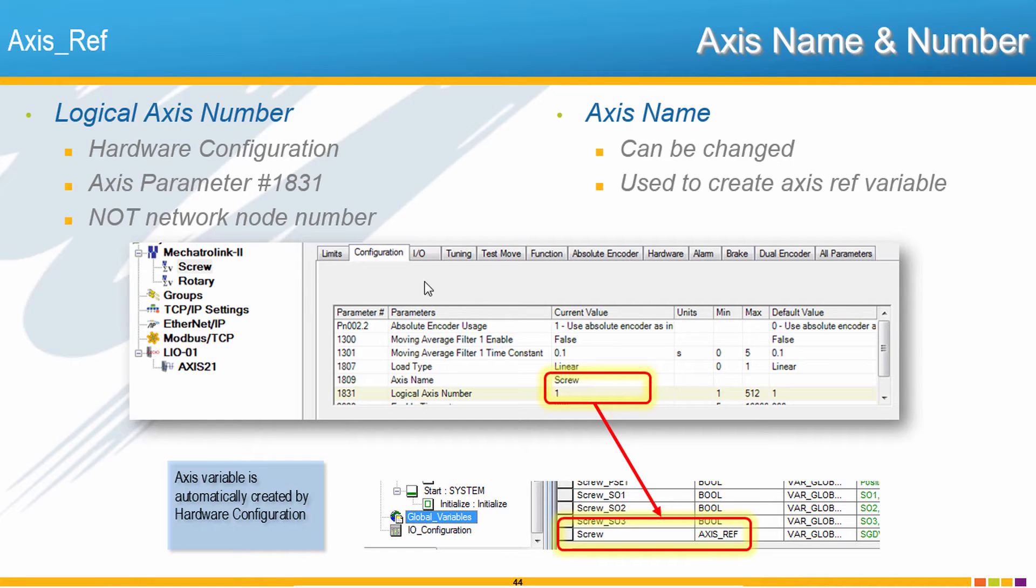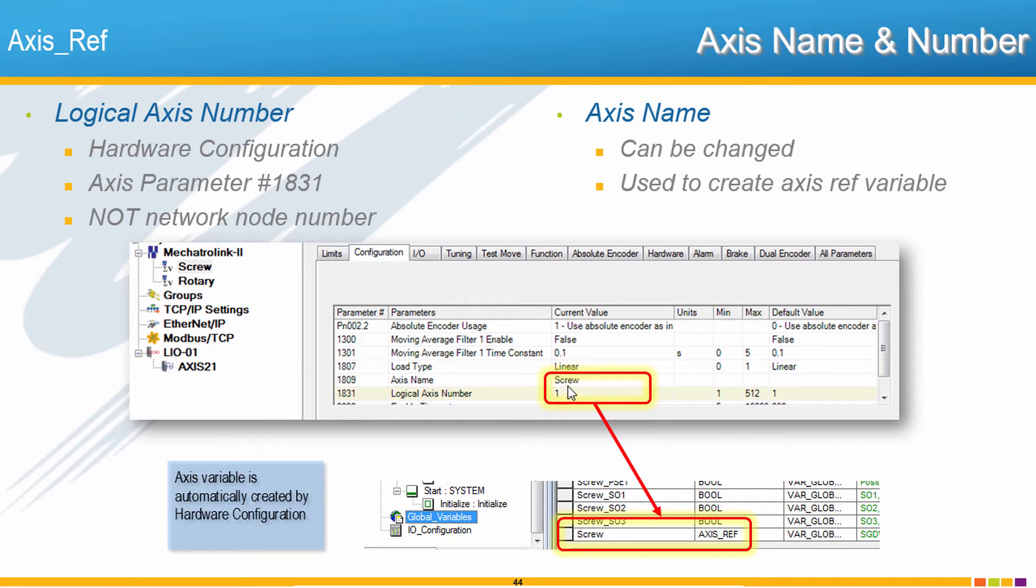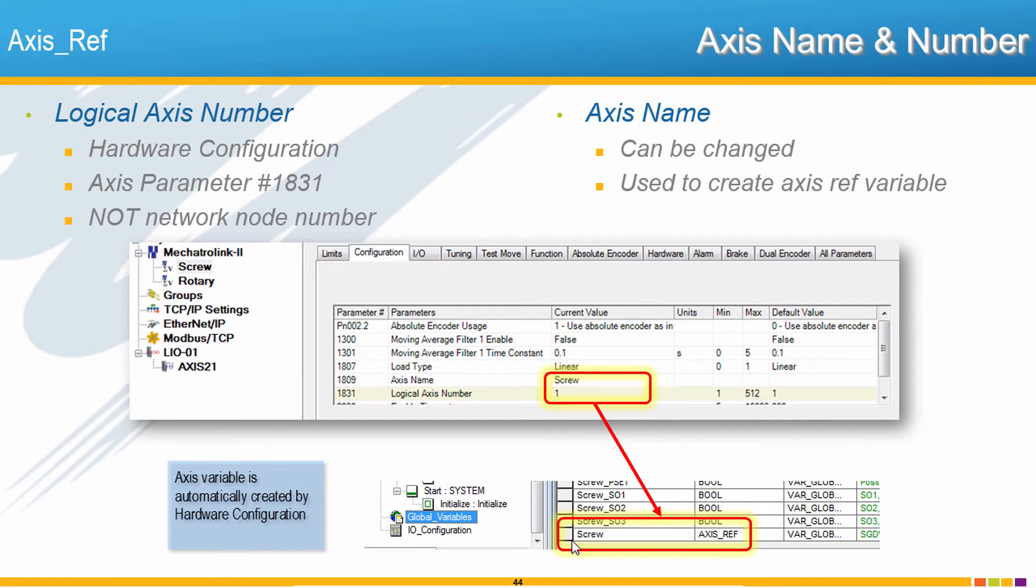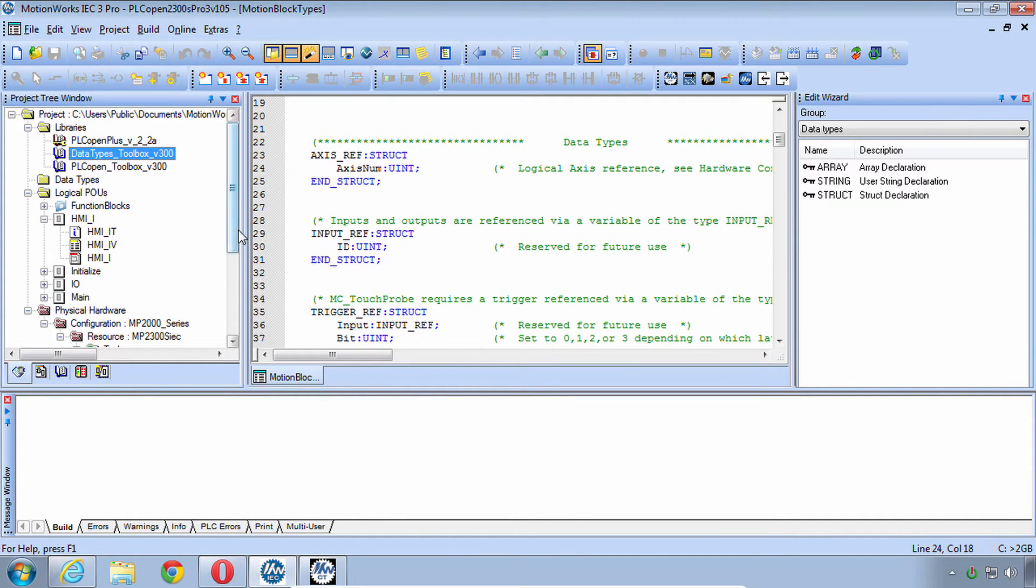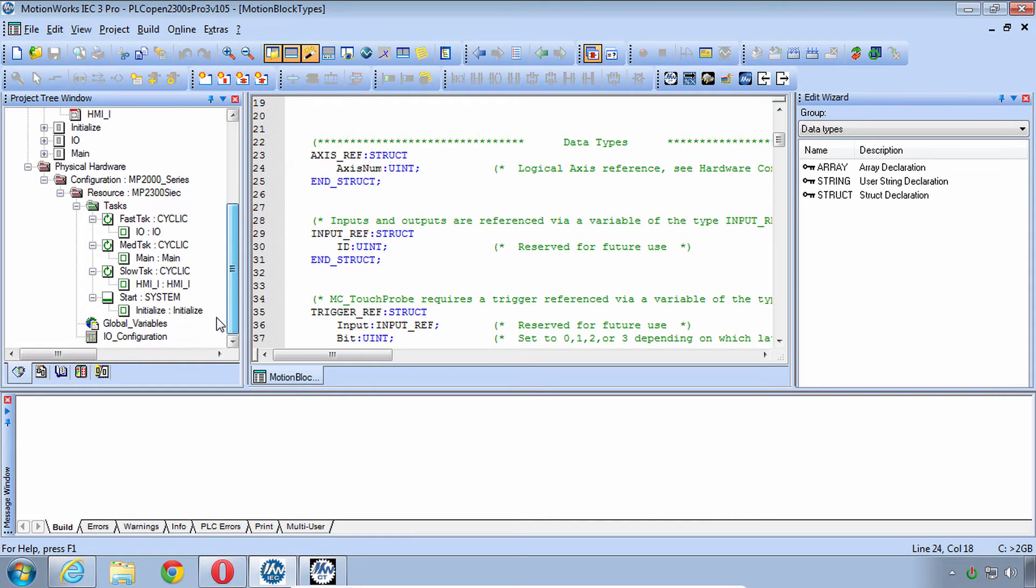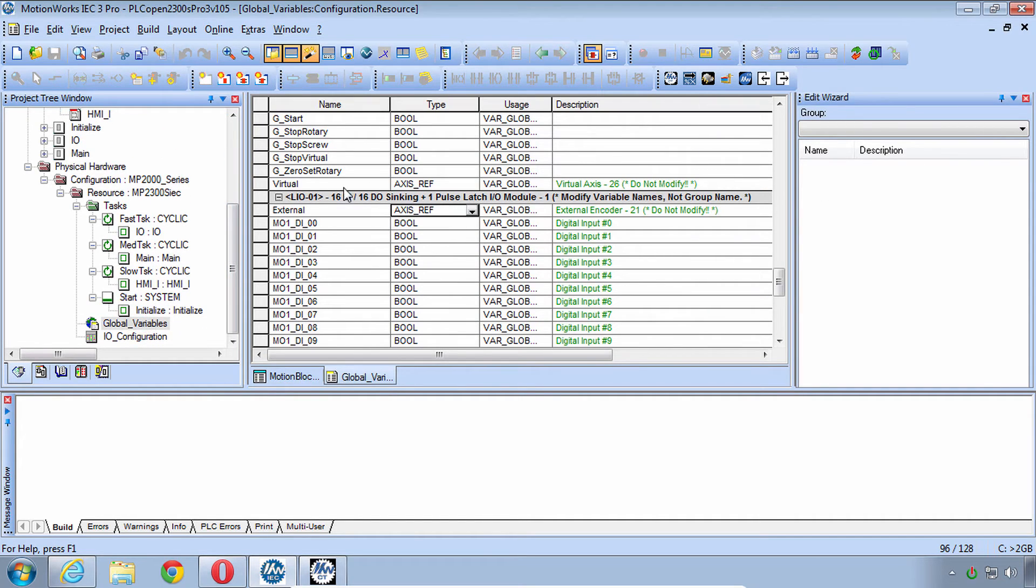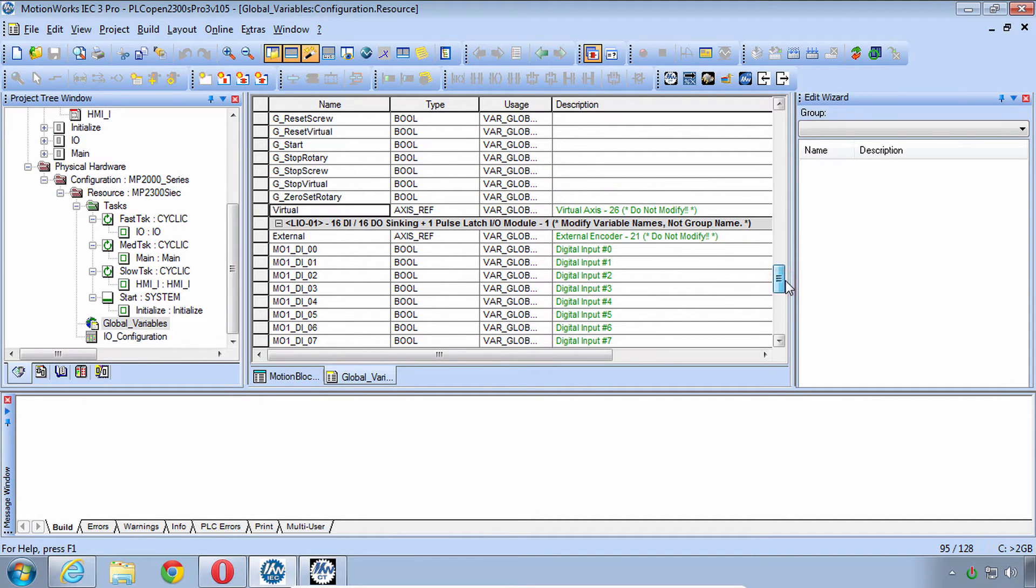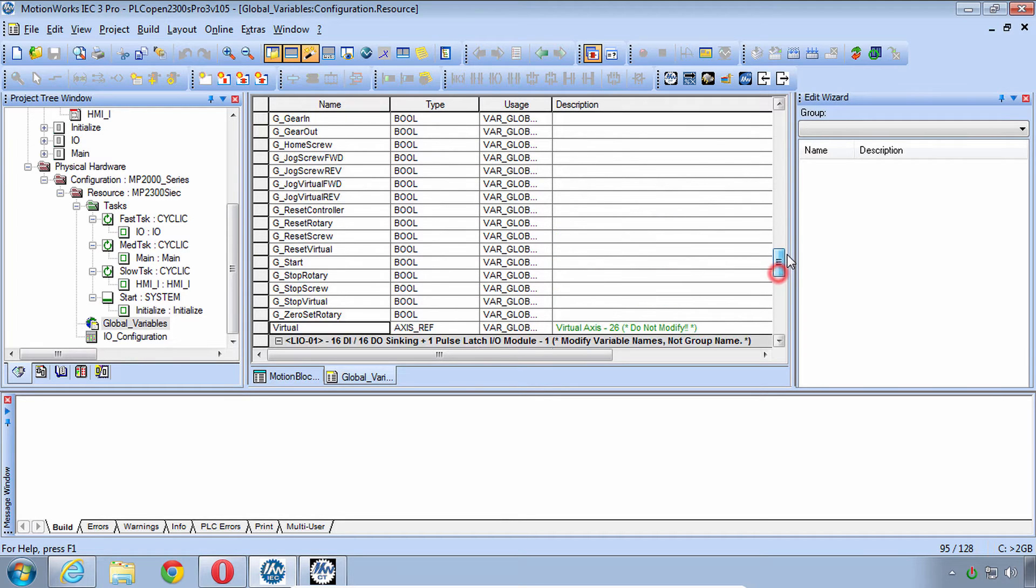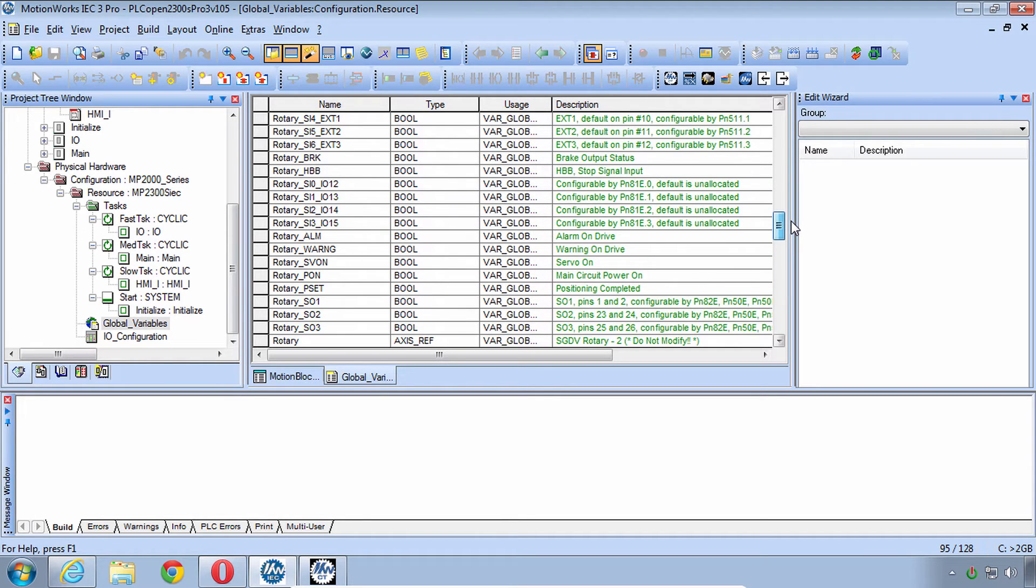What's of further interest in MotionWorks IEC version 3 is that right above the axis number is also the axis name. This name is important because this name has created an axisRef variable already for us. If you have version 2, you'll have to create this on your own. So back to the programming interface, I'll go to the project tab and come down here to global variables, and you see that these already exist.